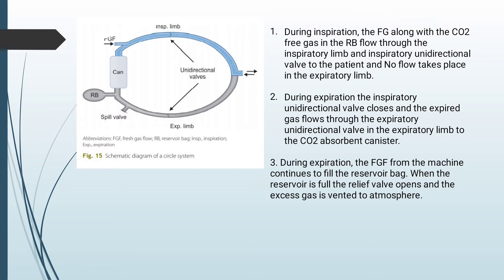During inspiration, the fresh gas with the carbon dioxide-free gas from the reservoir bag flows through the inspiratory limb (indicated by blue) and the inspiratory unidirectional valve to the patient, with no flow in the expiratory limb (shown in gray). During expiration, the inspiratory valve closes and expired gas flows through the expiratory unidirectional valve through the expiratory limb to the carbon dioxide absorbent canister. The fresh gas flow from the machine continues to fill the reservoir bag, and when the bag is full, the relief valve opens and excess gas is vented through the APL valve.